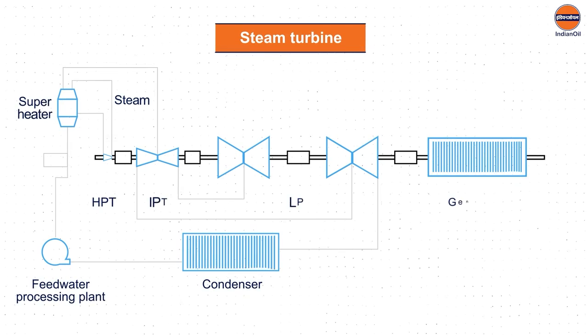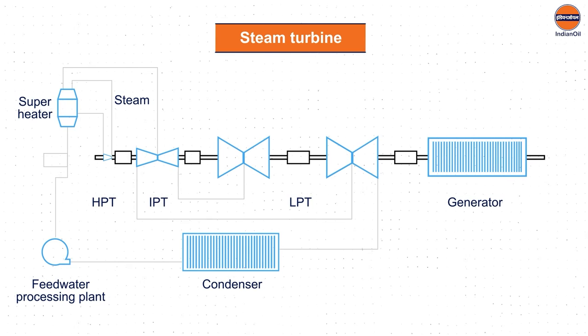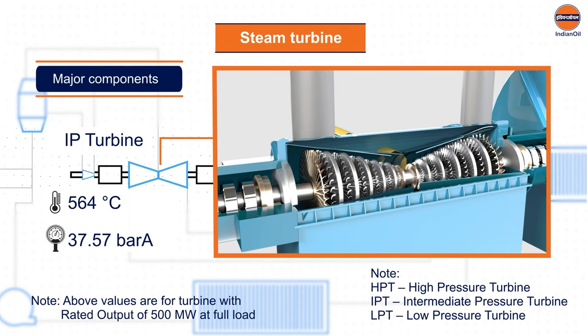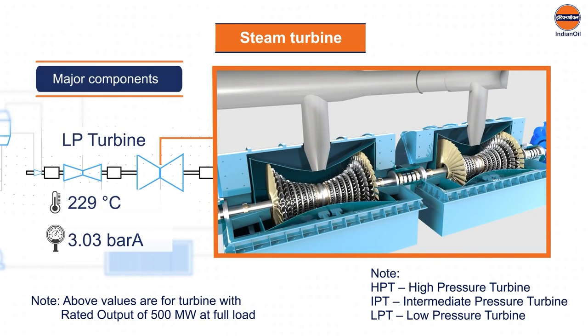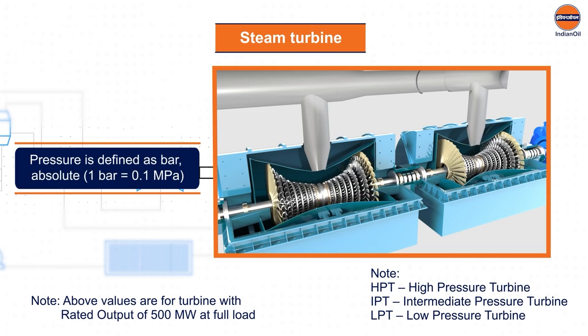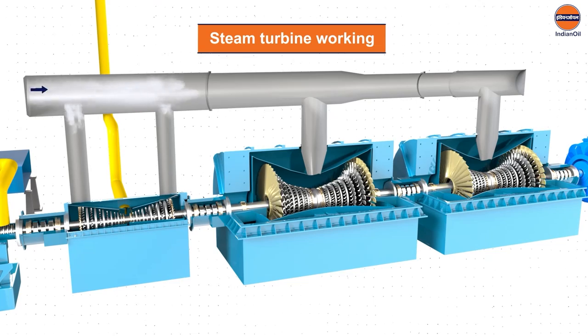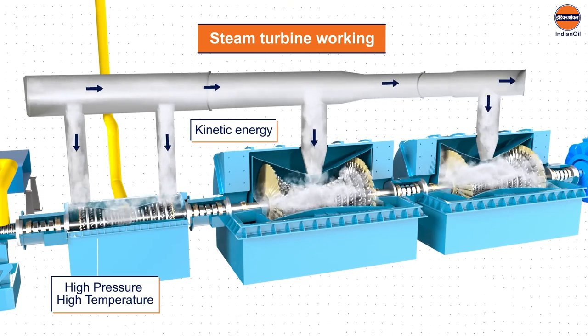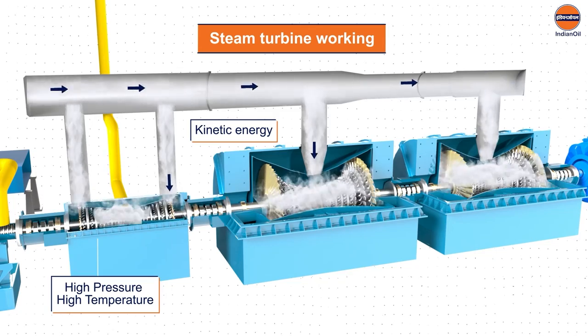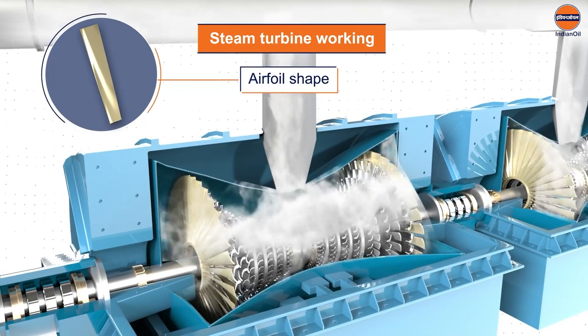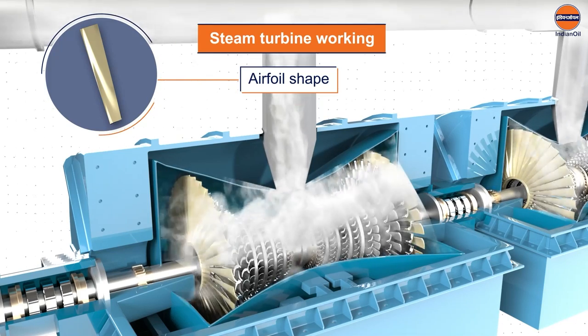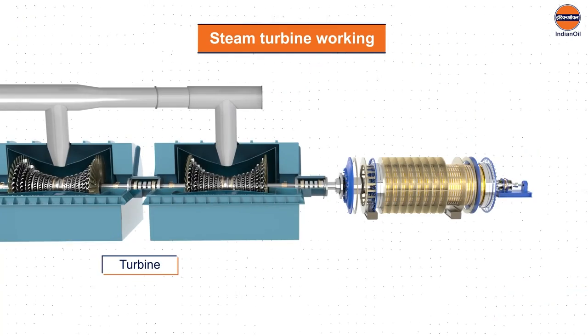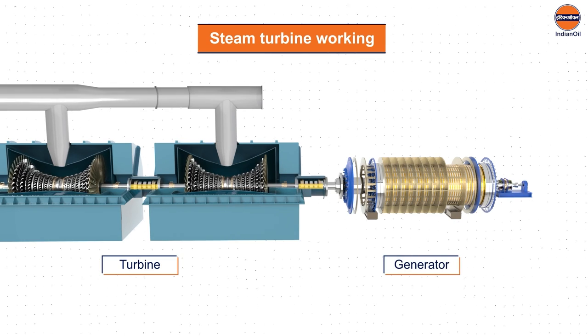Let's look at the steam turbine's schematic representation. A turbine can be divided into three parts: high pressure turbine, intermediate pressure turbine, and low pressure turbine. The high pressure, high temperature steam from the boiler enters the steam turbine through the nozzle as kinetic energy, turning the airfoil-shaped blades. These highly efficient blades enhance the flow of steam, causing its pressure and temperature to drop at the outlet. The rotating shaft from the turbine is connected to the generator shaft and causes rotation in the generator.